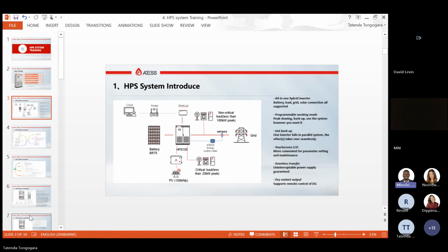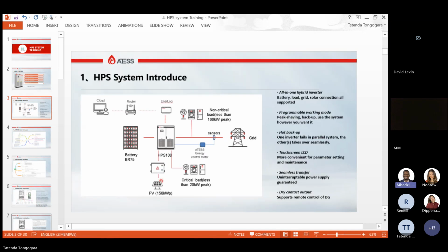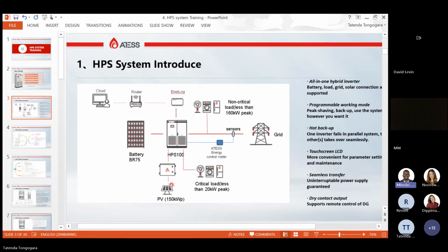So I see that with the HPS 100, you have an Atess energy control meter. Yes, that's on the grid side. So I could basically have some non-essential loads, and then feed any excess back up until the grid point on the energy meter side, and then just feed any excess to the non-essential loads. That's possible, right? Yes, that's possible. So this is our energy meter, and then the non-critical loads.